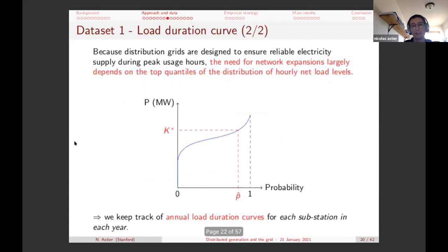The reason you would do that is that when you plan for an electricity grid, what you ultimately care about is being able to supply power with very high reliability most of the time. So you want to plan the grid to reliably supply customers for the high load events, but maybe not all of them, because planning for everything is costly. As a planner, you would choose some reliability threshold P hat, and having ranked these hours in increasing order of load enables you to quickly assess how much capacity you need. If you say, I want a reliability of my grid of P hat, you can move all the way up to the load duration curve, and that tells you how much capacity you need for the grid.